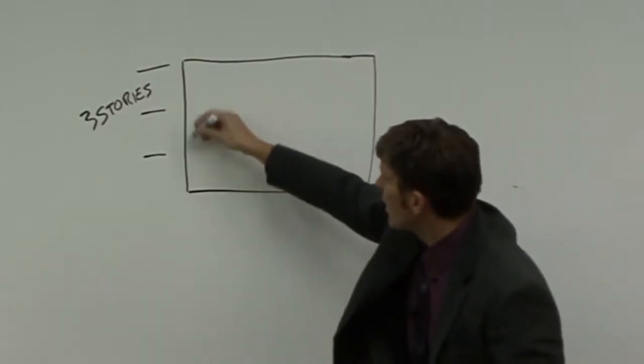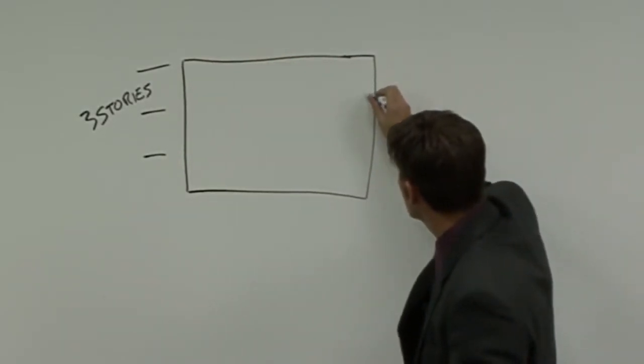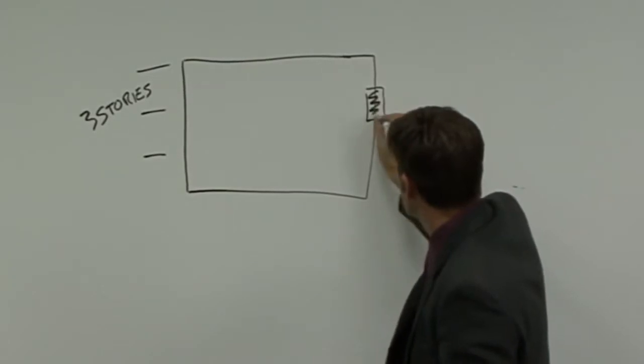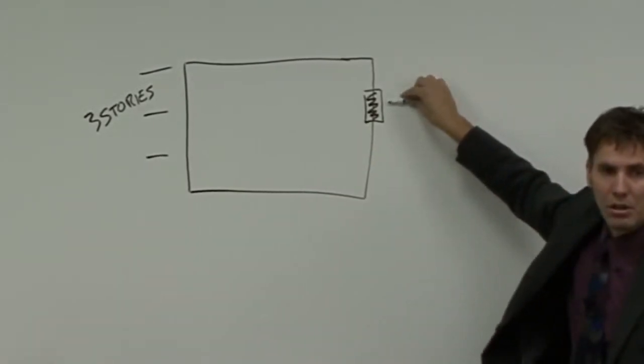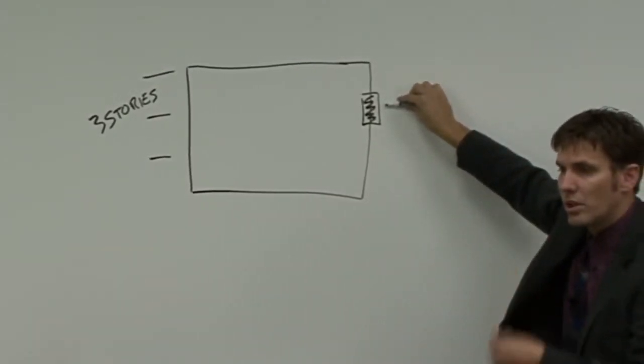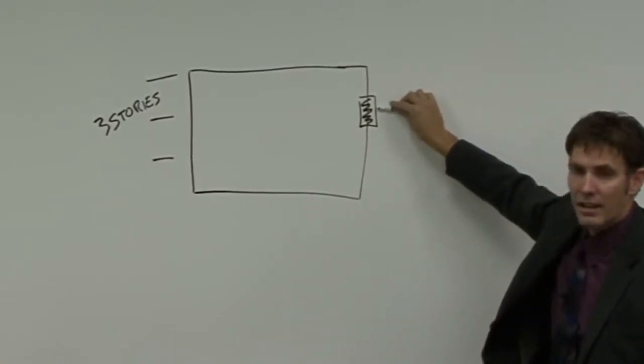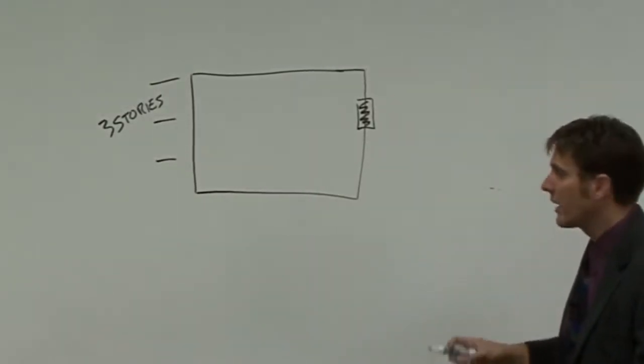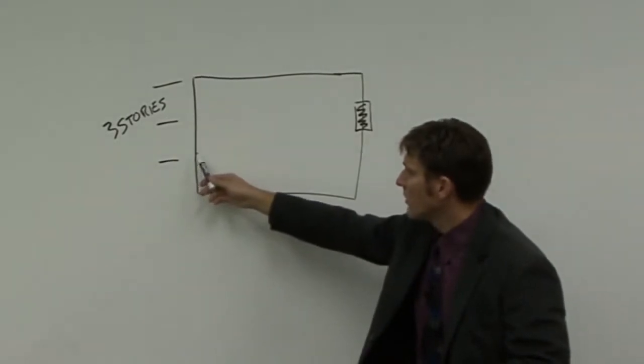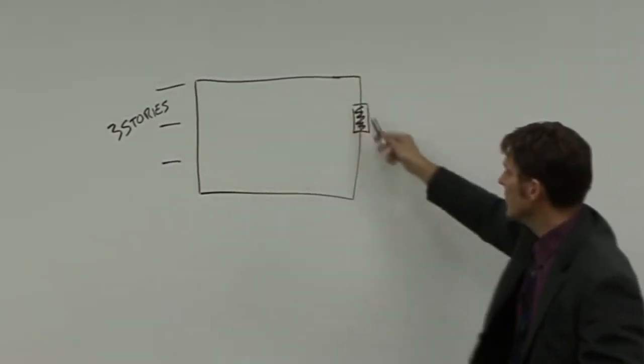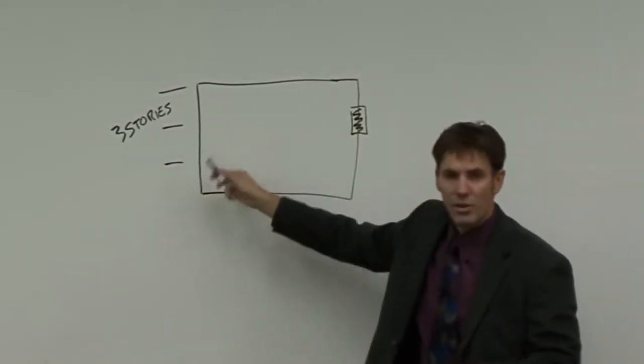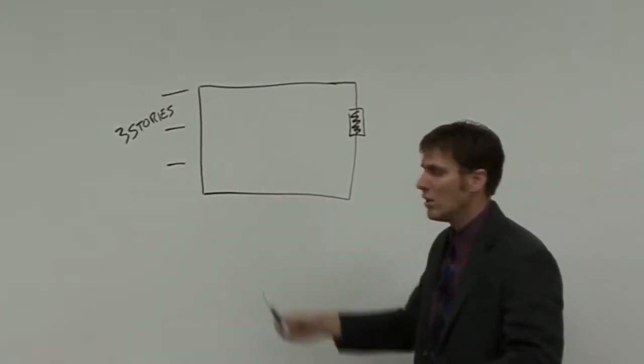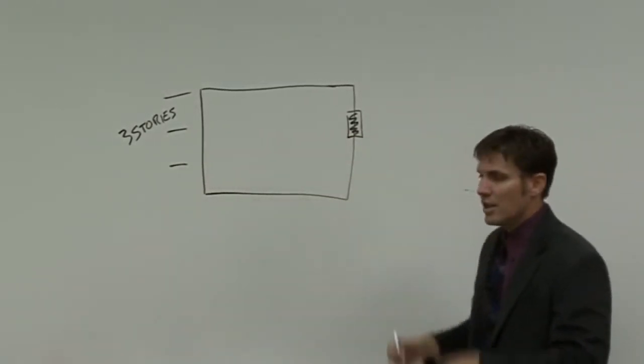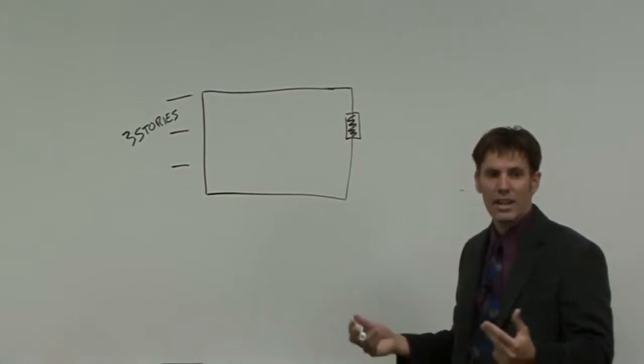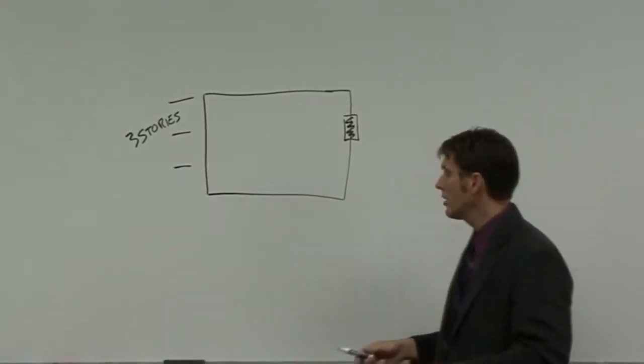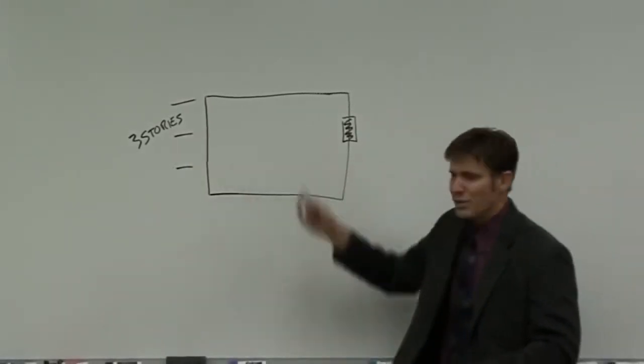And we need to move the water out to this building so that we can get it out to maybe a heating coil, maybe a fan coil unit system with a cooling coil inside of it. Maybe this is an air handling unit with a cooling coil inside of the air handling unit. My goal or my objective is to move the water throughout this loop and back so that I can either heat it back up or cool it back down. We're moving that water out to the system components so that we can have heat transfer and provide comfort to our building occupants. Well, how do we do that?